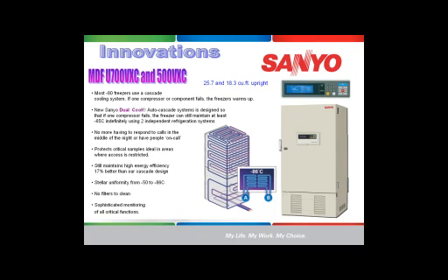Another thing is it gives us extremely stellar uniformity from minus 50 to minus 86, which is something that traditional ultra-low freezers are not able to do: give you good uniformity throughout the whole range of what an ultra-low freezer will operate. There's also no filters to clean in this because of the efficiency of this unit, and on top of that, we have some sophisticated monitoring systems of all critical functions on how that freezer operates.